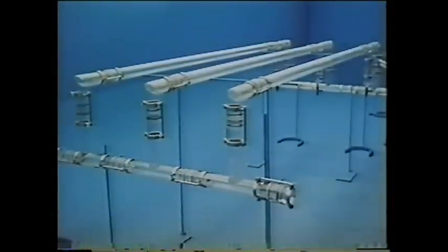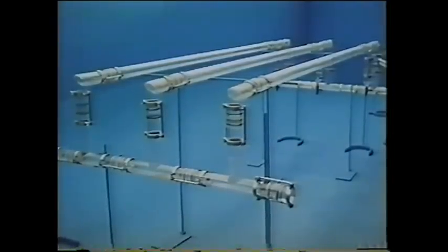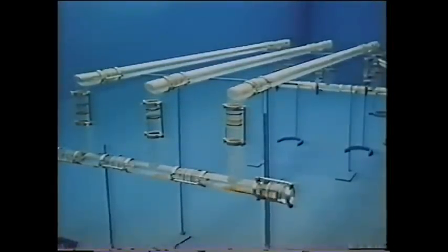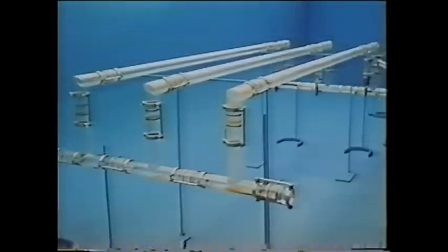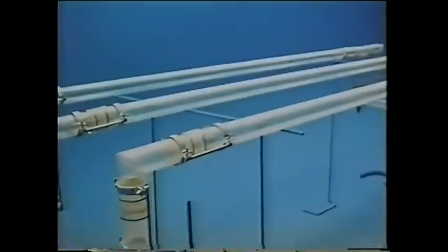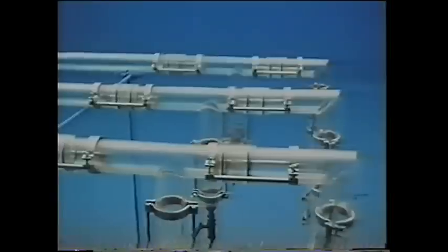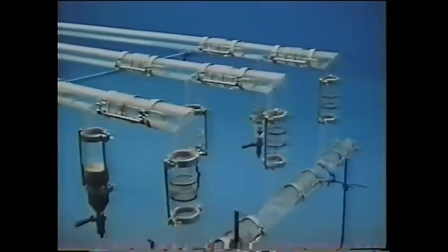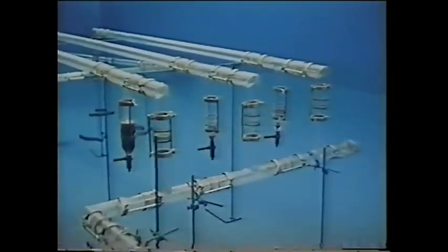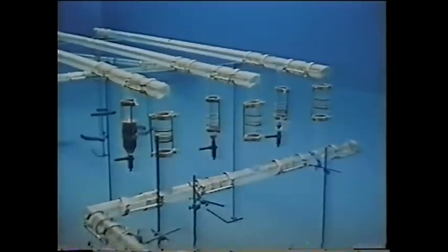This is the pipeline situation at the inlet side of a gas delivery station. The gas comes from the left and divides over the meter runs. It appears that the liquid carried along accumulates at the last meter run. The liquid separator in this particular meter run is already half-filled, while the liquid traps in the other two runs are still practically empty. The separator in this meter run must therefore be designed to handle all the liquid.